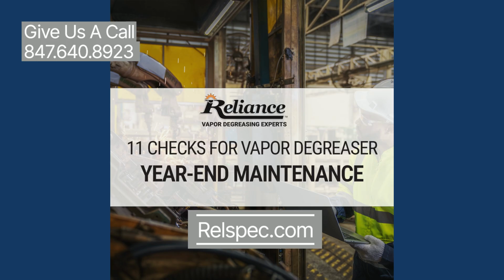Check 6. Check, clean, and replace your heating elements. Heating elements are fairly robust, but accumulated debris on the elements over time will cause them to operate inefficiently and ultimately shorten their life cycle. Note, many companies annually change out their heating elements as part of an annual periodic maintenance cycle.